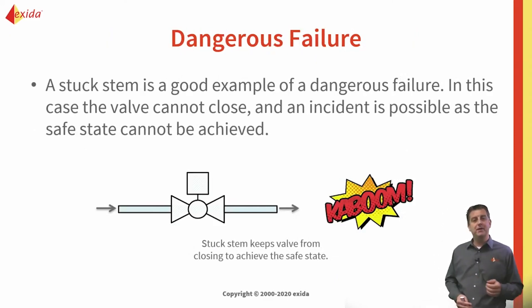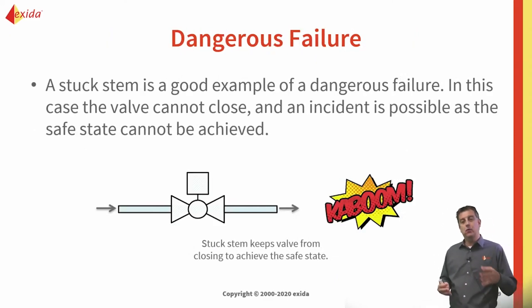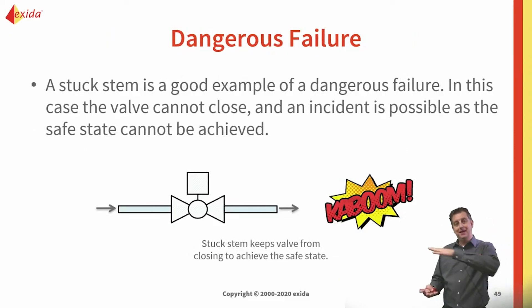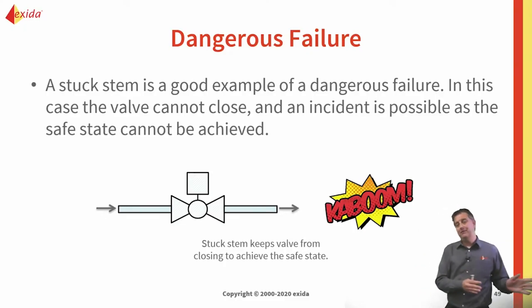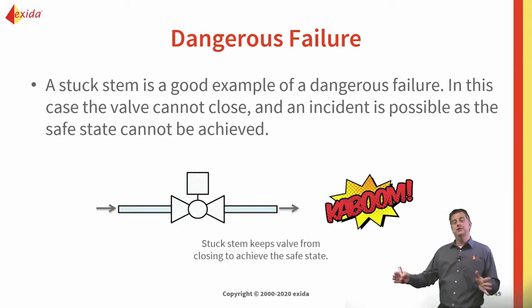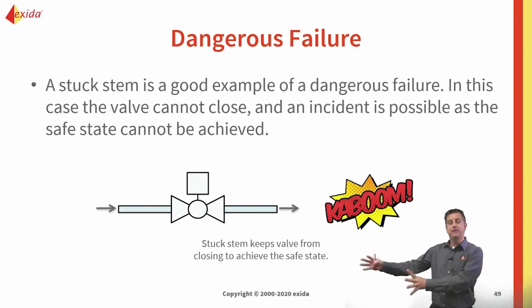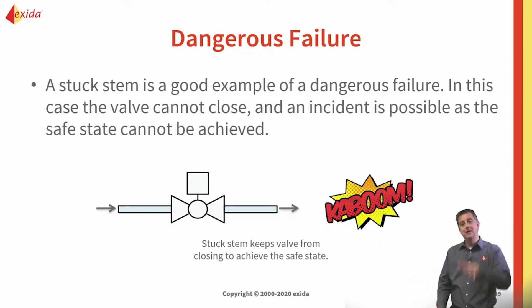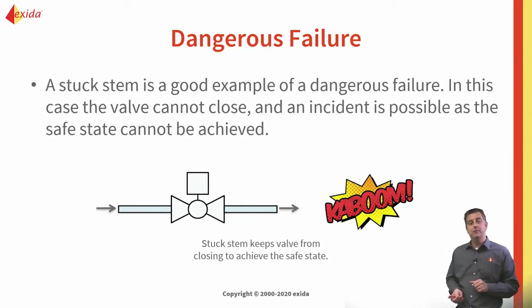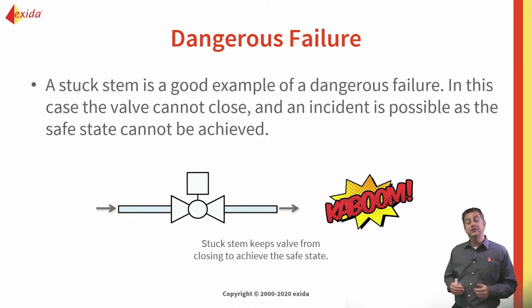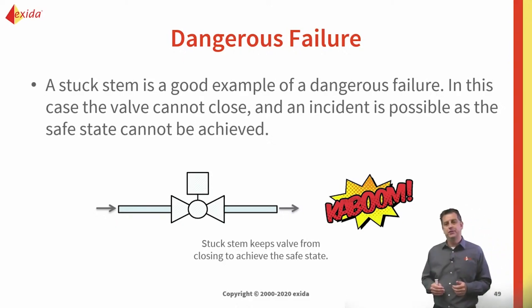A dangerous failure would be any failure where that valve can no longer close. So for whatever reason the process needs to stop — maybe there's a high pressure event or an overfill about to happen — I want to stop flow, and for whatever reason that flow cannot be stopped. The valve is stuck in the open position.